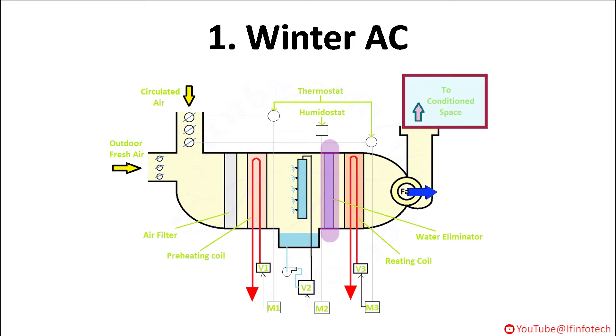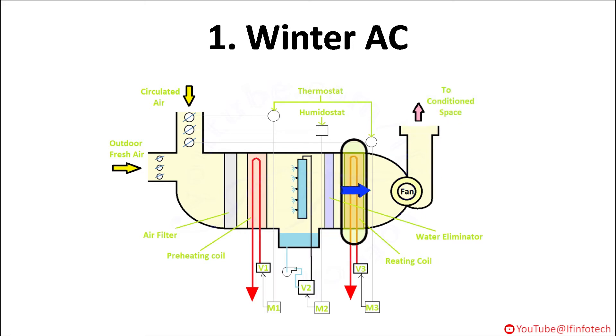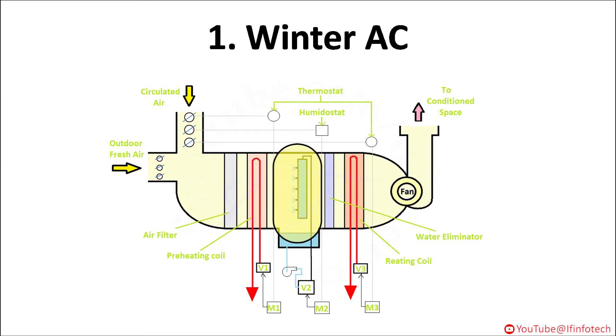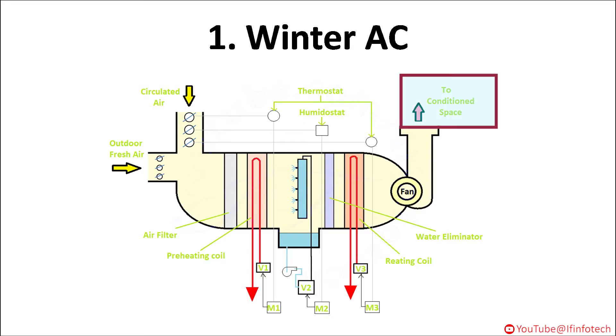Before passing air to the conditioned space, it is reheated to adjust temperature and humidity. The preheating coil and reheating coil are provided with valve V1 and valve V3 that open or close by motor M1 and motor M3 respectively. The quantity of air passing through the air conditioning system depends upon the load, so the quantity of air supply is controlled with the help of dampers.